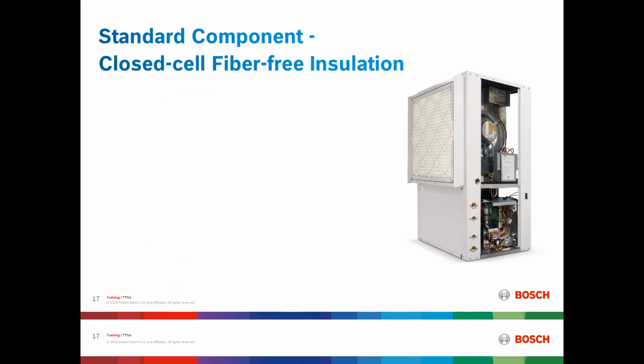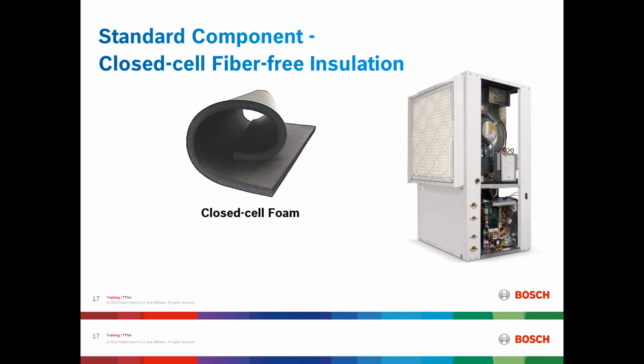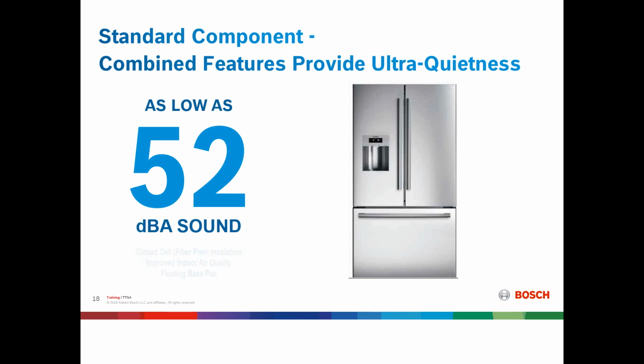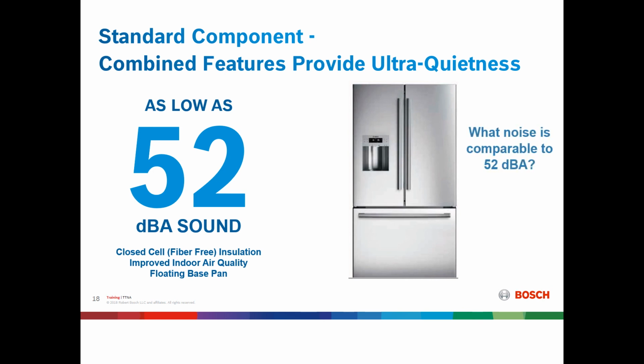The cabinet itself will have closed-cell fiber-free insulation. This insulation improves indoor air quality and allows us to meet less than a 2% air leakage rate per the ASHRAE Standard 193. With these combined features of closed-cell fiber-free insulation and a floating base pan, the SM-REV-V has a sound decibel rating as low as 52. What noise is comparable to a 52 decibel? A refrigerator is comparable.